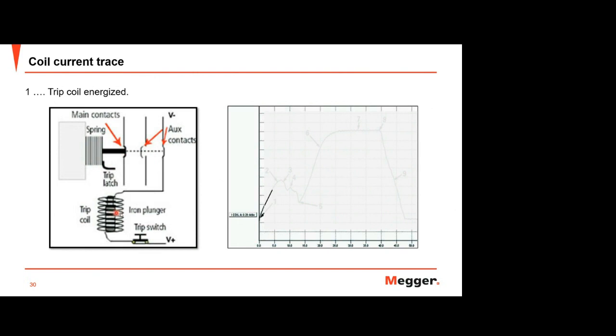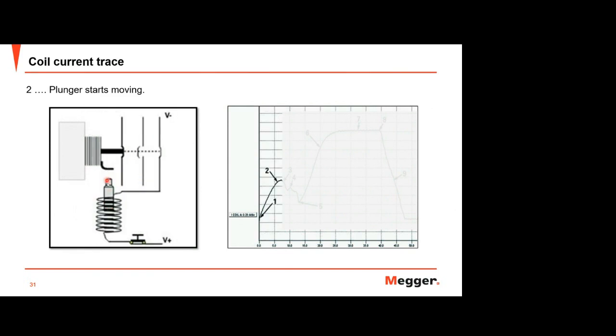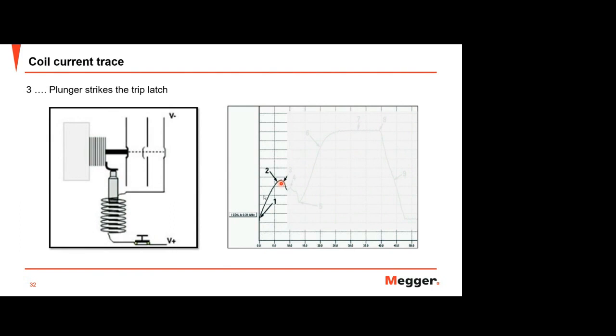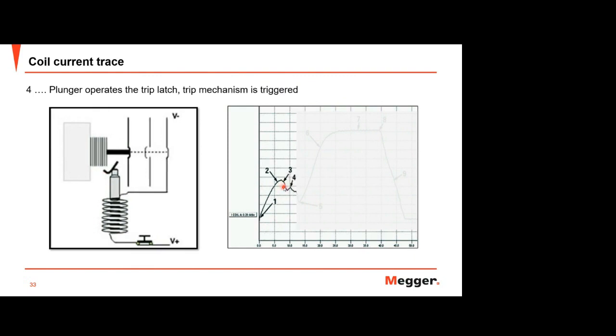from the coil. So when the breaker is still closed, the coil current is also in rest position, and when the plunger starts to move, the current rises until here, but then stops a little bit after the touch, because this latch component is also considered mechanical. So if there is some grease issue or some mechanical issue, this will resist the plunger movement. So this is why at the first touch the current will reduce again, decrease until the latching part is moving, and then it increases again until this level.